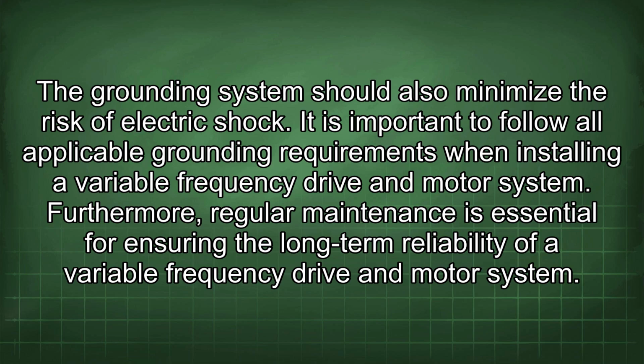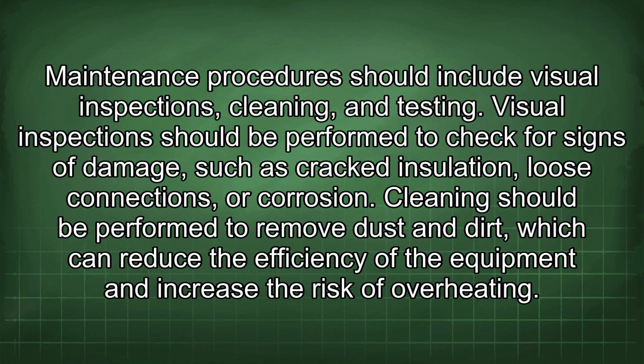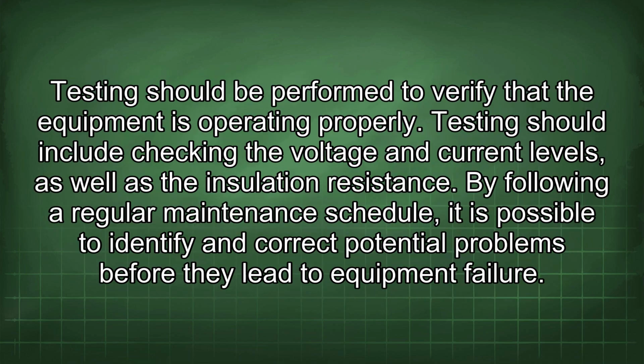Furthermore, regular maintenance is essential for ensuring the long-term reliability of a variable frequency drive and motor system. Maintenance procedures should include visual inspections, cleaning, and testing. Visual inspections should be performed to check for signs of damage, such as cracked insulation, loose connections, or corrosion. Cleaning should be performed to remove dust and dirt, which can reduce the efficiency of the equipment and increase the risk of overheating. Testing should be performed to verify that the equipment is operating properly. Testing should include checking the voltage and current levels, as well as the insulation resistance.